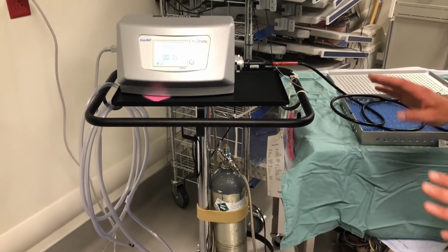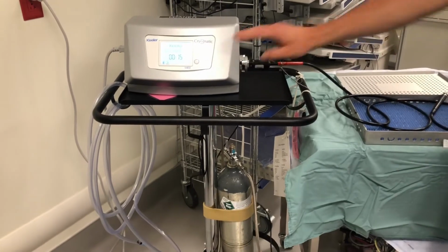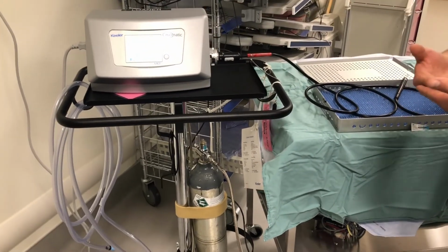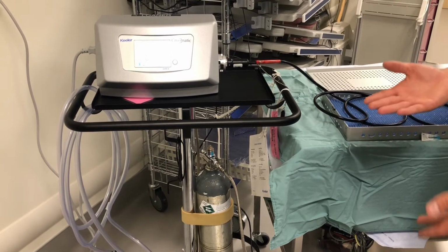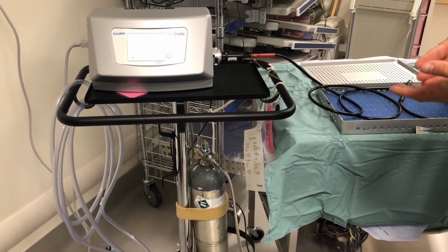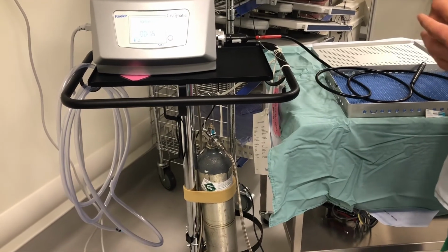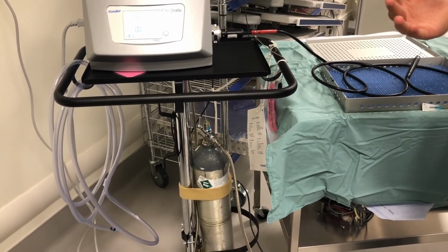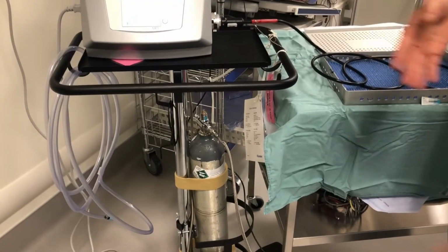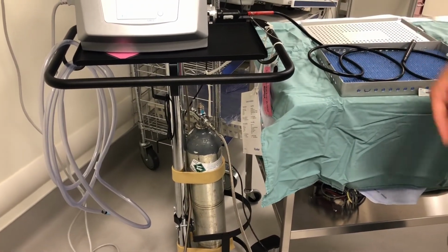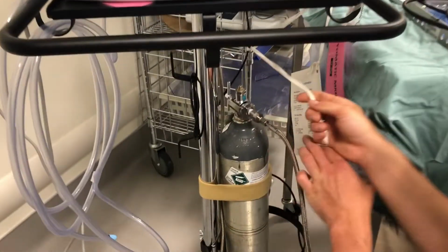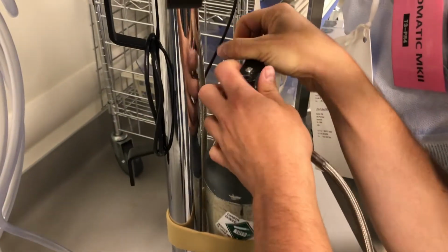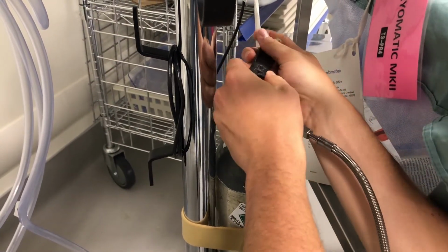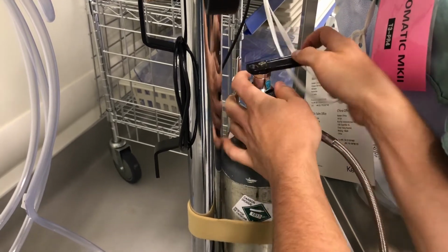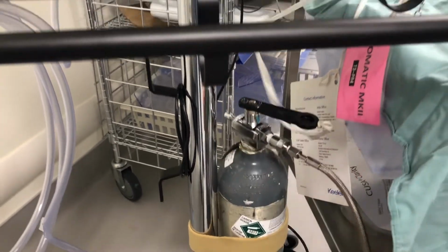Okay, so now we've shown how to set up the machine, how it's applied, how you can keep track of the cold application. Next thing we're going to go over is how to shut off the machine. So the first thing I would suggest doing is turning off the gas, because that tends to be forgotten about, and if the gas is left on while the machine is off, we could run out, so then the next time it's used you have to go running for a tank. So we're going to turn off the gas first, and it's going to be a righty-tighty to turn it off. Okay, so tighten that, that's off.